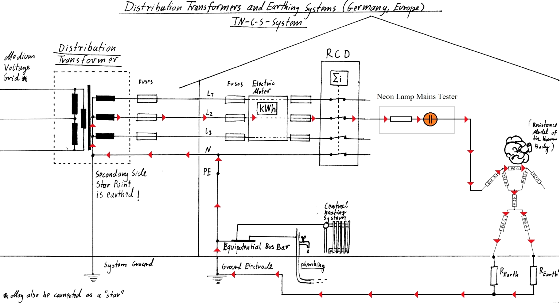The current flows from the distribution transformer through all the fuses and the RCD, through a current limiting resistor and through the neon lamp, lighting it up. Then the current returns via your body and the ground and over PE and PEN to the transformer. The RCD doesn't react. The current sum is not 0 amperes, but it is very small and well under 30 milliamperes, and even well under 1 milliampere, not being dangerous for an adult person.